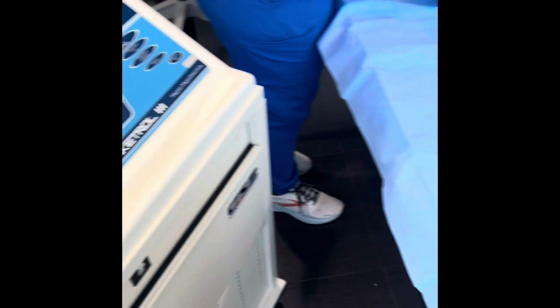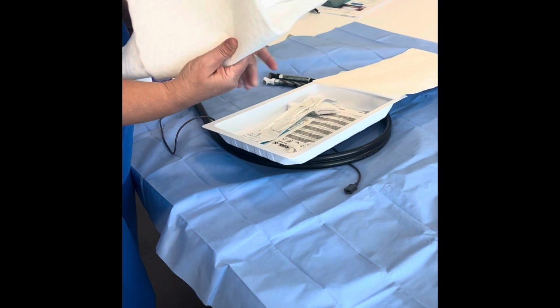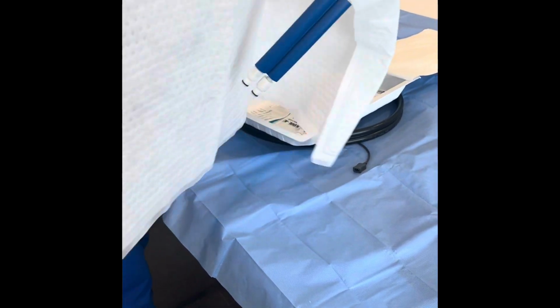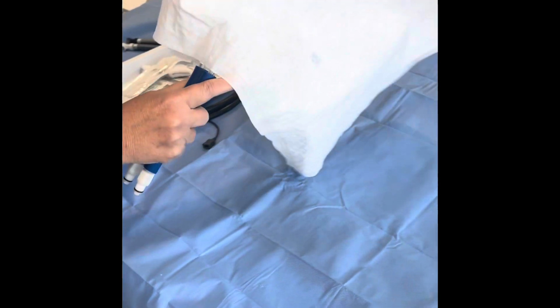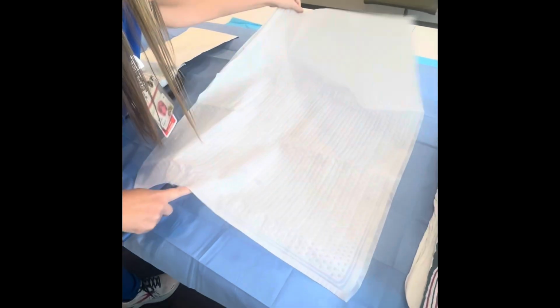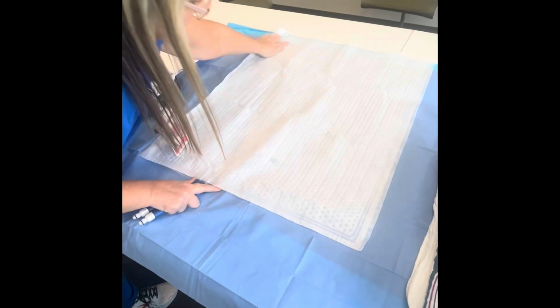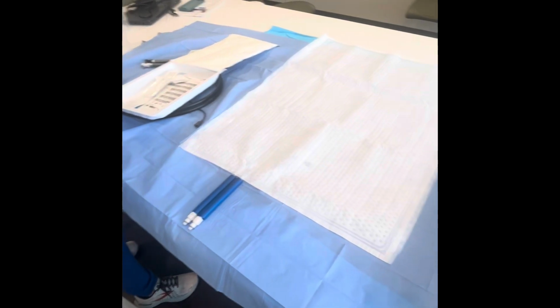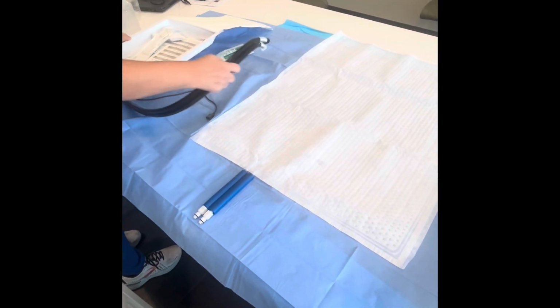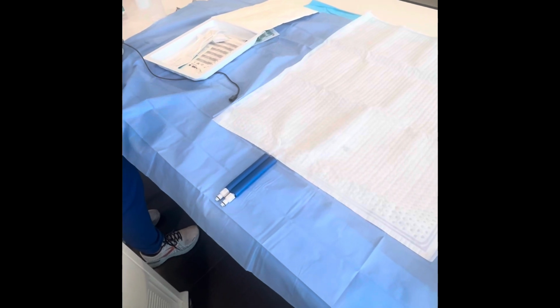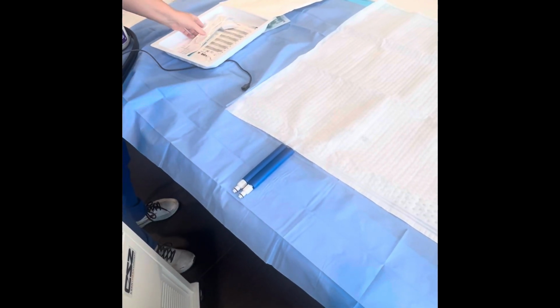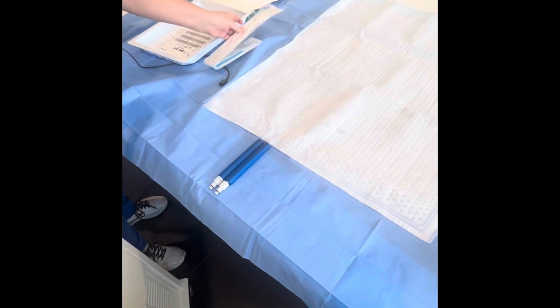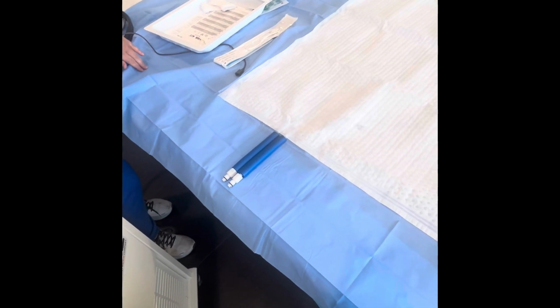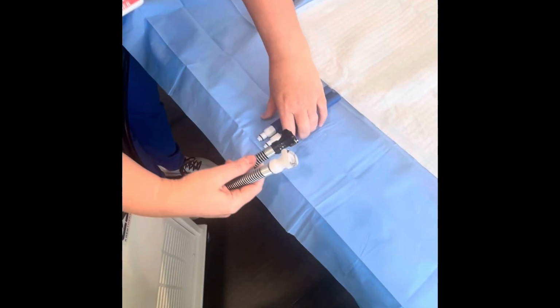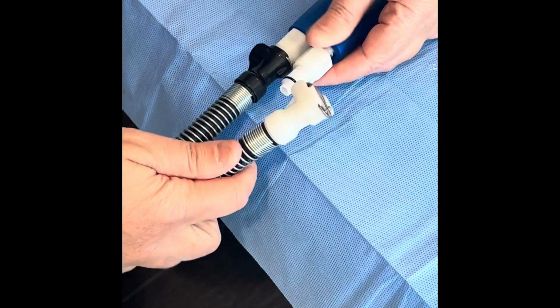Open your cool kit. Place your cooling blanket on the radiant warmer. Ensure it is flat with no kinks in your tubing or blanket. Clamped or kinked tubing will impede your water flow through the blanket, which may interfere with your cooling process. Connect your water cables to the blanket.